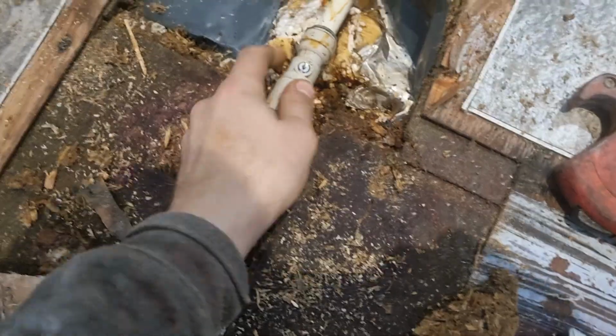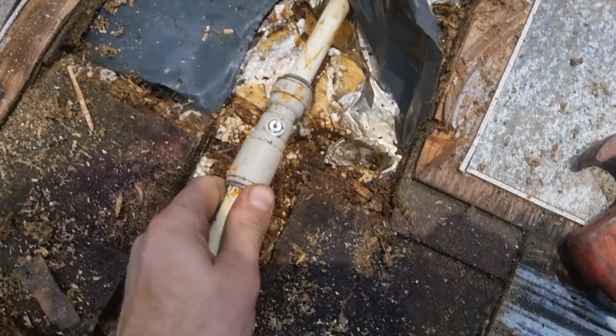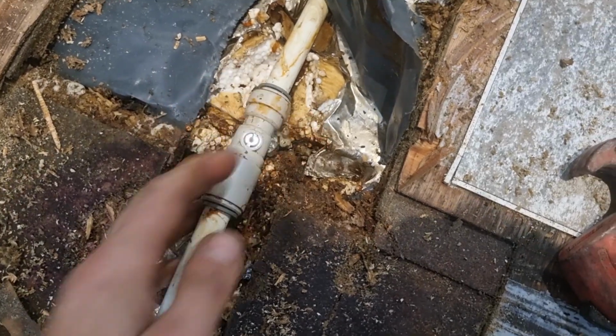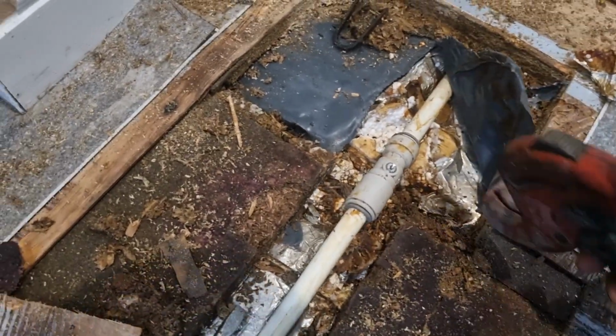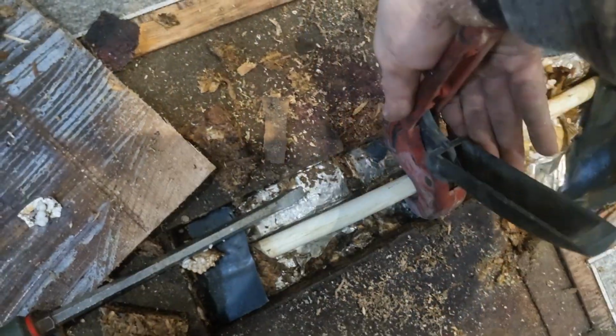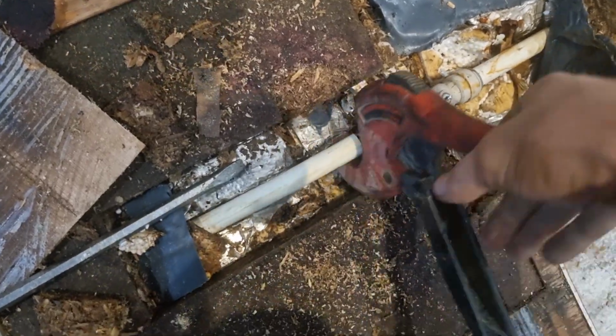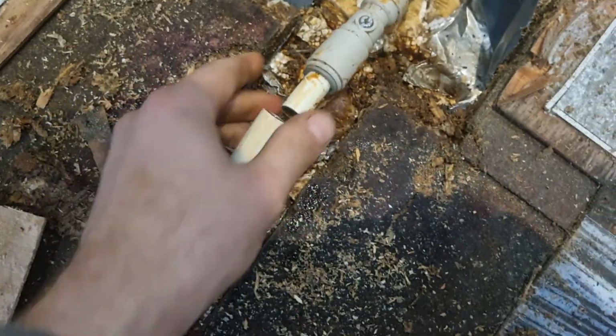This is where it's been leaking. I haven't got any pressure in the system, but that's not even the right fitting for that pipe, because that's a Speedfit fitting, I think, and that's an Uponor pipe. I'll tell you what, we'll cut into that, because I've got to try and make a repair on this anyway. That is definitely Uponor, isn't it? Is it Speedfit or Uponor? Might be Speedfit. No, it is an Uponor type pipe. It's got a barrier.